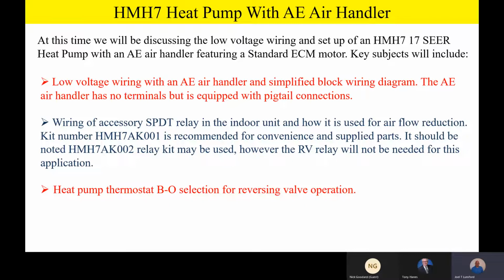And kind of write this down or make a little note of it. That HMH7AK002 kit is required for the variable speed air handler, but it is not required for this air handler. But you could use it in a pinch because you just end up having an extra relay on the board. So the kit number 001 is actually recommended for this application. But let's say you get into a situation for some reason or another, you can't get the kit, or you're out of the kit, or you're stuck putting this thing in. All you can do at this point is very, very simple. Just take a single pole double throw relay, like a little peanut relay, as long as it's got a 24-volt coil and single pole double throw action on the contacts, and then supply your own bi-flow filter dryer. So you can make up your own 001 kit, is what I'm trying to say, very easily. Just make sure you have a bi-flow filter dryer.